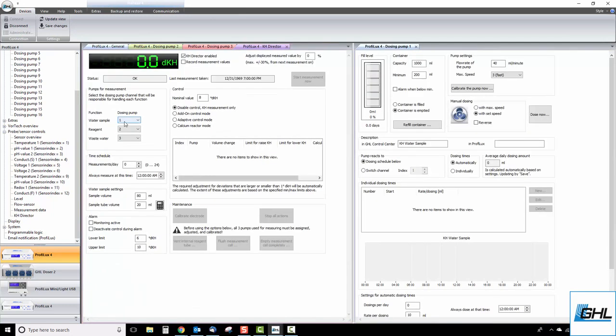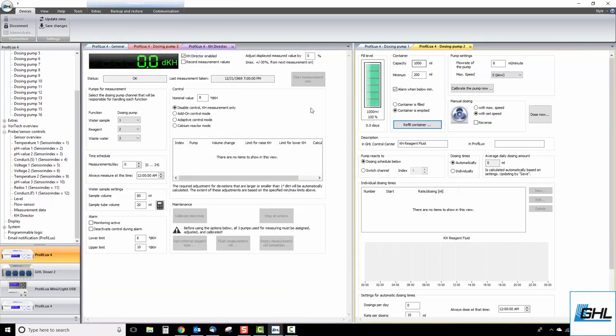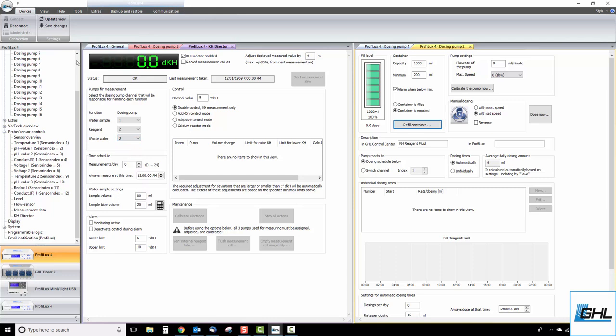Next, select the dosing pump channel you want to use for your reagent. In our example, we used dosing pump channel 2, so we'd select dosing pump 2 for the reagent function. Lastly, select the dosing pump that will be assigned as the wastewater pump. Once these pumps have been assigned, click Save Changes.